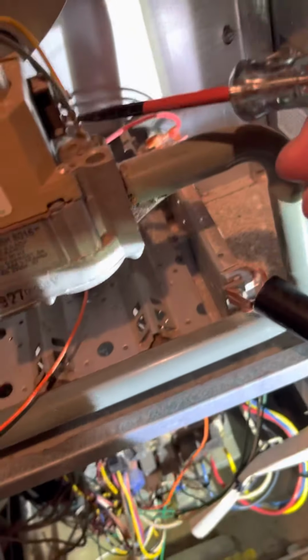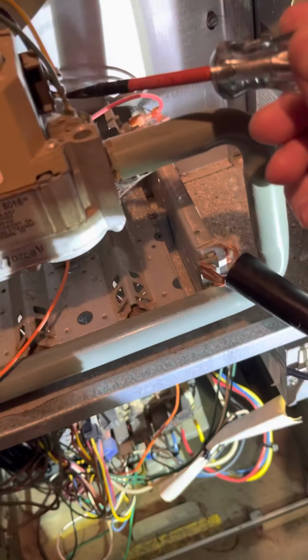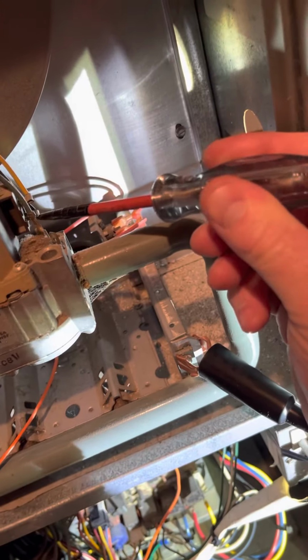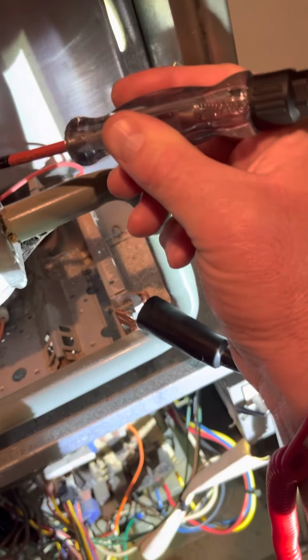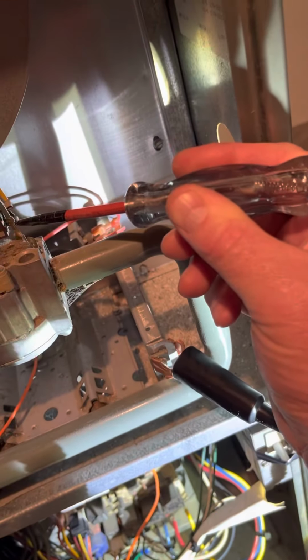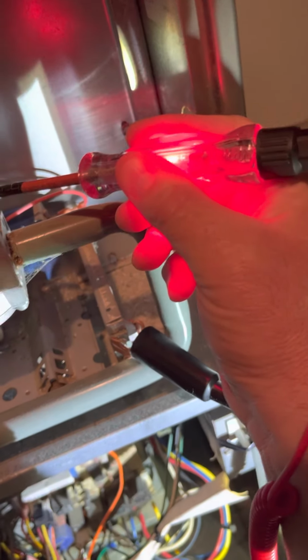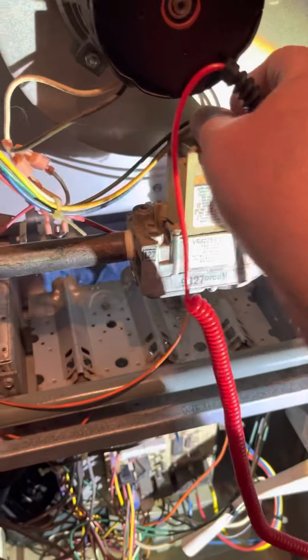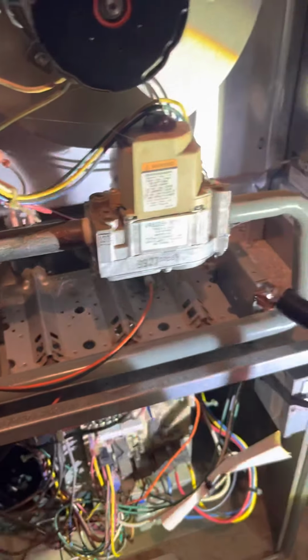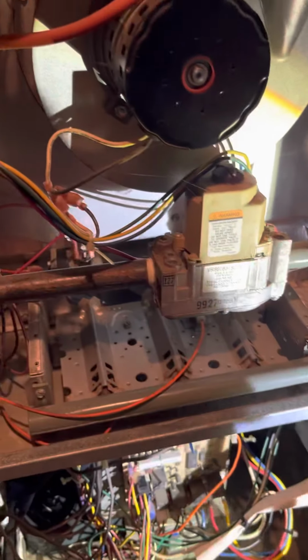We'll go over here to the gas valve, and you can see there's no light, so I don't have any power going to the gas valve at this moment. When it tries again, it'll send 24 volts to the gas. There we go, see? So we have 24 volts, we have main burner. I'm going to shut this off again because I want to cool the heat exchanger down before I turn it off.